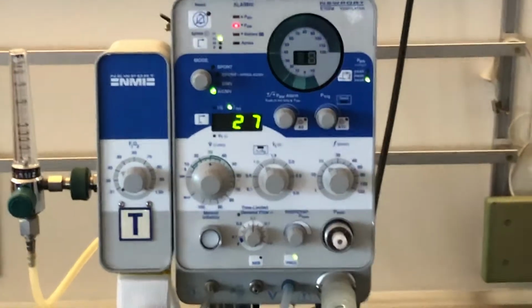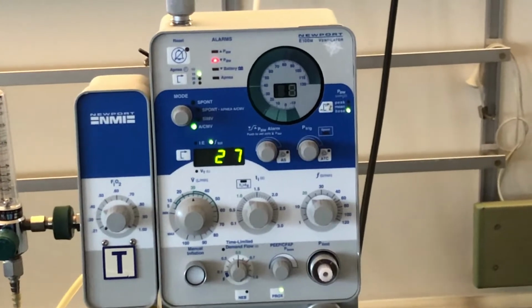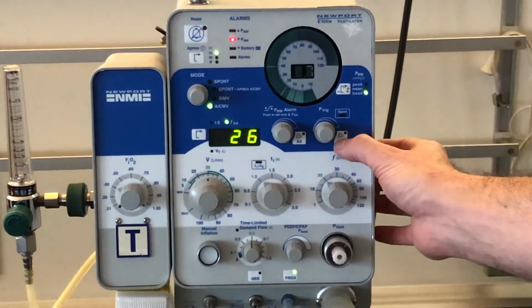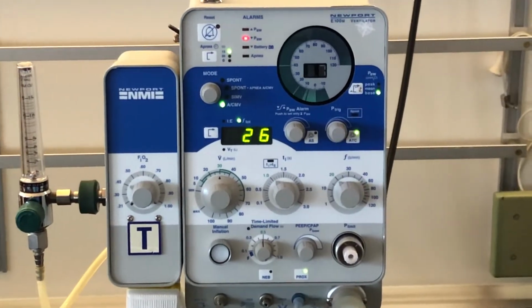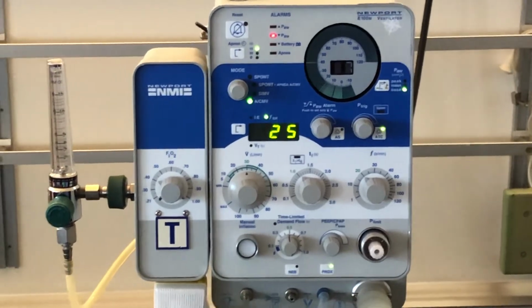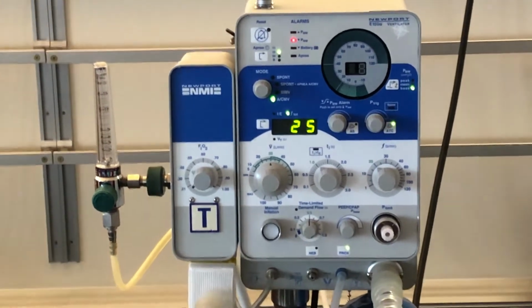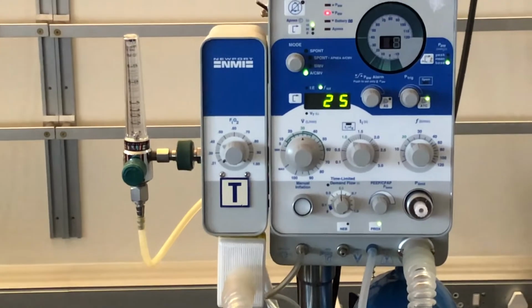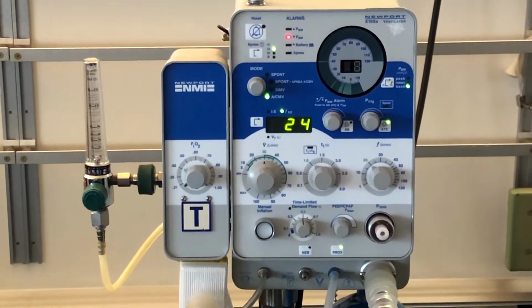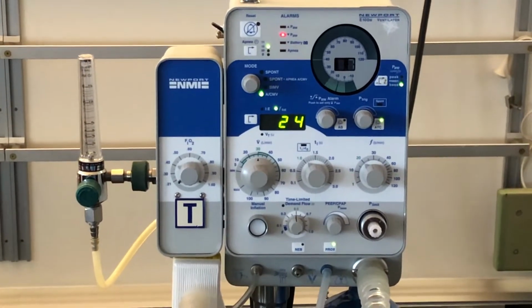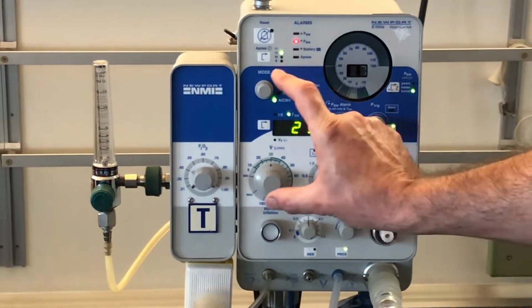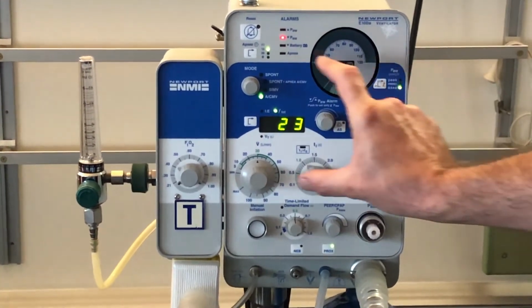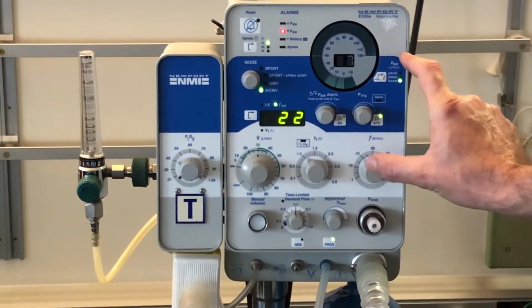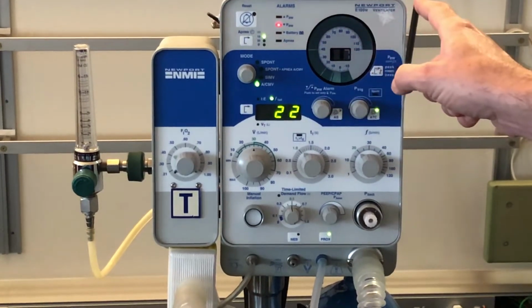Once we get our PEEP setting where we want it to be, and we want the patient to trigger again, then we can switch the trigger control on again on the ventilator. And now if I squeeze the bag, I'm able to make the patient trigger the ventilator as was happening earlier. So that goes through the basic settings of a mode like assist control and the monitoring panel of the machine.